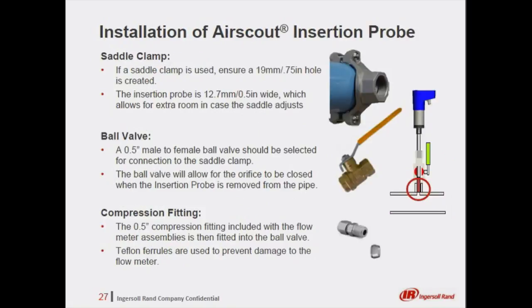In many cases, when installing an insertion probe flow meter, a saddle clamp will be the preferred method for installation. To successfully install, ensure a 3/4 inch hole is created. The insertion probe is 1/2 inch wide, which allows for extra room in case the saddle adjusts slightly. It is also recommended that a 1/2 inch male to female ball valve be connected to the saddle, allowing for the orifice to be closed when the insertion probe is removed from the pipe.